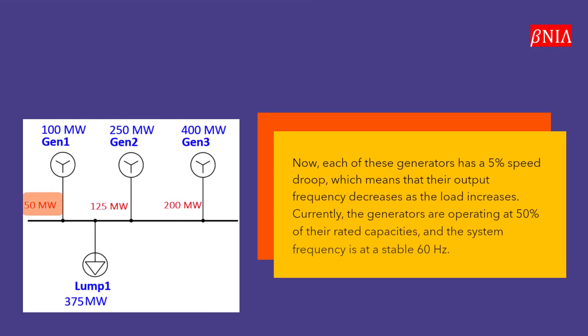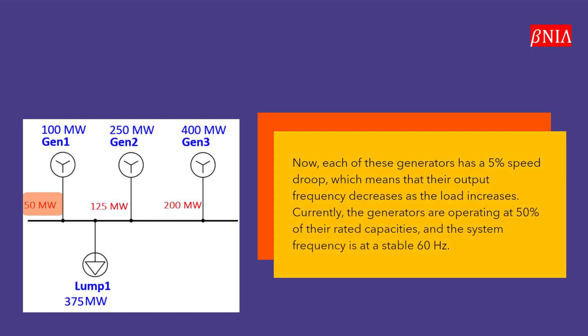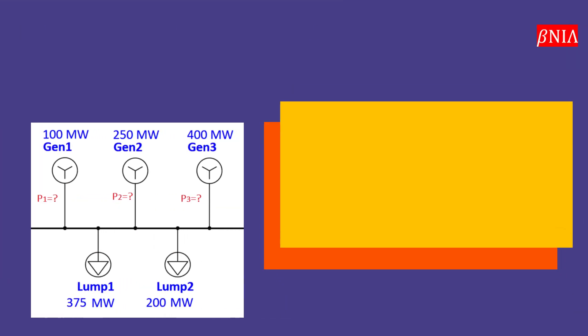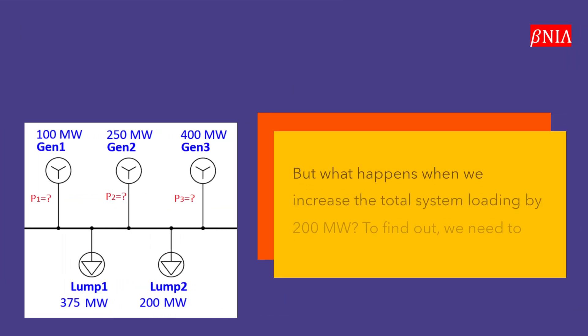Each of these generators has a 5% speed droop, which means that their output frequency decreases as the load increases. Currently the generators are operating at 50% of their rated capacities and the system frequency is at a stable 60 Hertz.